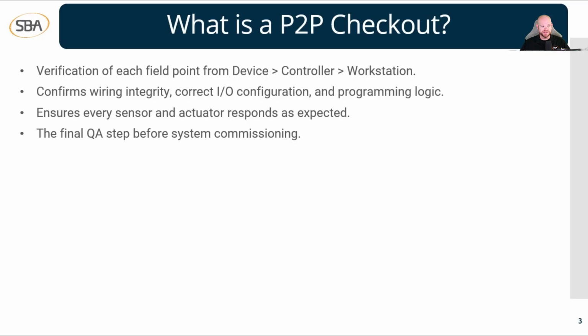So again, we start off by verifying all these things. The next thing it does for us is confirm our wiring integrity. As you know, we have to wire every one of these devices up, so we need to make sure they're wired correctly. That's part of this process: confirming that our wiring is correct, that we're reading good values from our inputs, and that we are able to command the outputs through that good wiring. The next thing is ensuring that we have the correct I/O configuration in our software and on our controllers. This is confirming that points are landed where they're supposed to be, and that devices are wired up to where they're supposed to be.